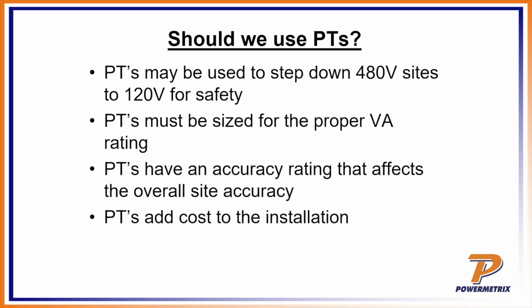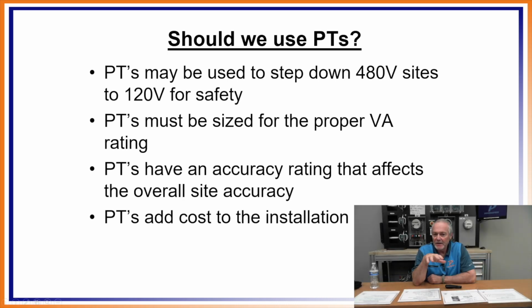Okay, PTs. Like I said, we did the class on that earlier, as far as testing them and everything. With us, you never can say always, but almost all the time it's going to be step downs, right? So it says the PTs may be used to step down 480-volt service to 120. In that case, you'd use a 4-to-1, so you'd get a fourth coming out of the secondary side on those PTs. They must be sized properly for the VA rating, like we said.